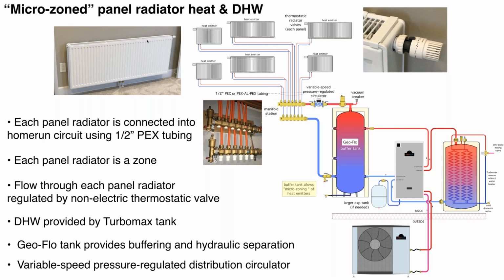And interestingly, the lower the water temperature that you operate these radiators at, the higher the percentage of the total output goes as radiant heat versus convective heat. So low temperature operation of these panel radiators is definitely favorable, definitely possible.